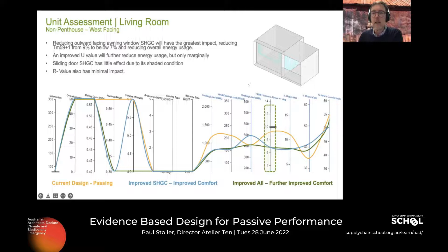We run through the thousands of simulations, choose the current design, choose a few improvements, and map them out to see how they perform. This analysis also shows us peak cooling load, peak heating load, and other factors. We can also see what has minimal impact—in this case, for this unit type, the R value of the insulated wall, the little bit that there is, had little impact, so we know we don't have to worry about that one, which is very helpful.